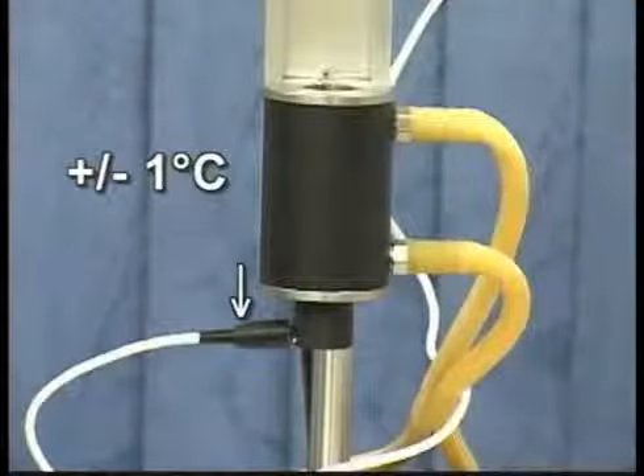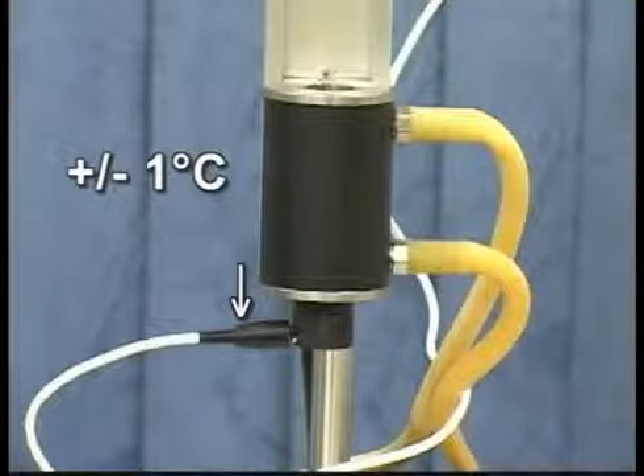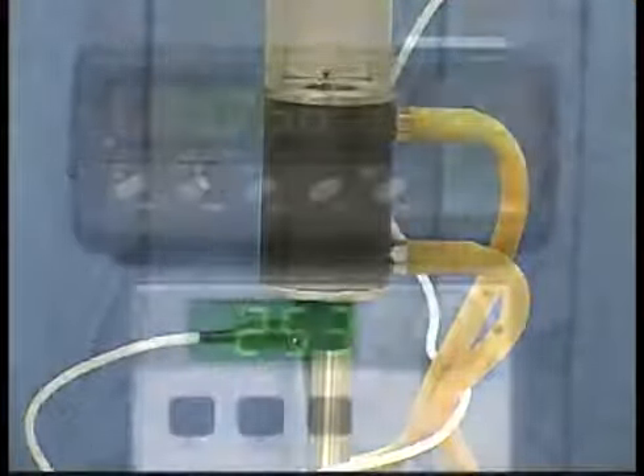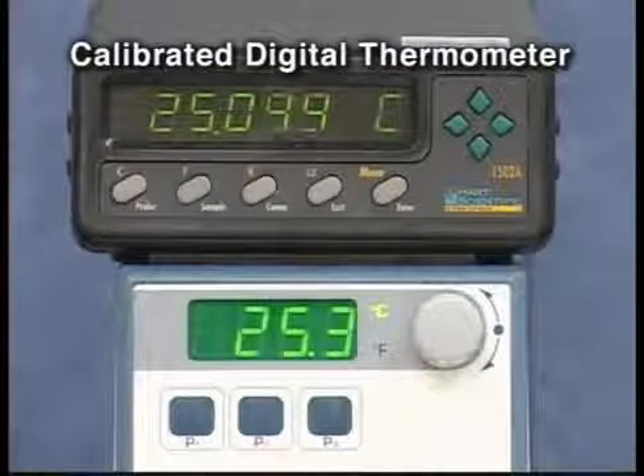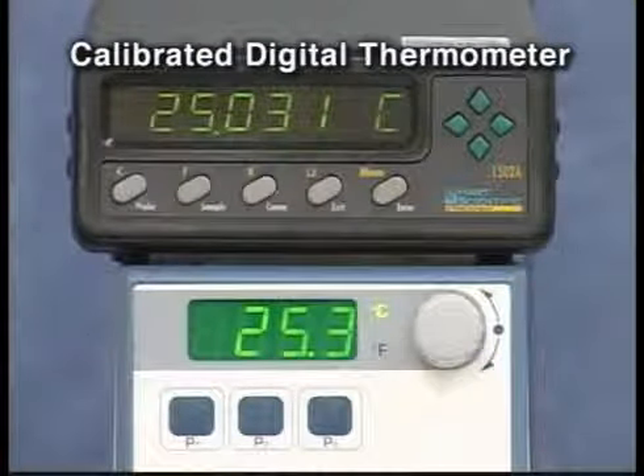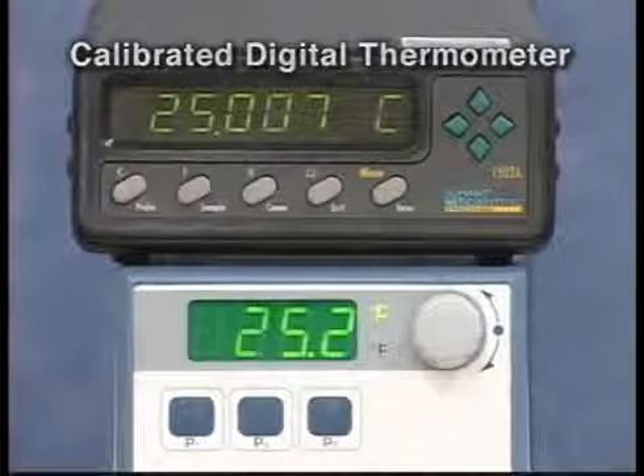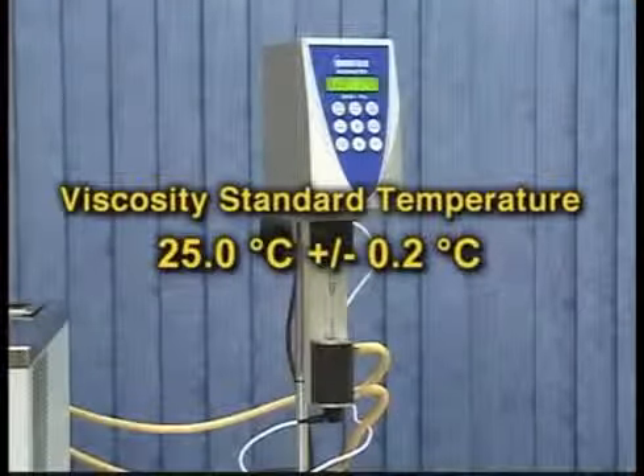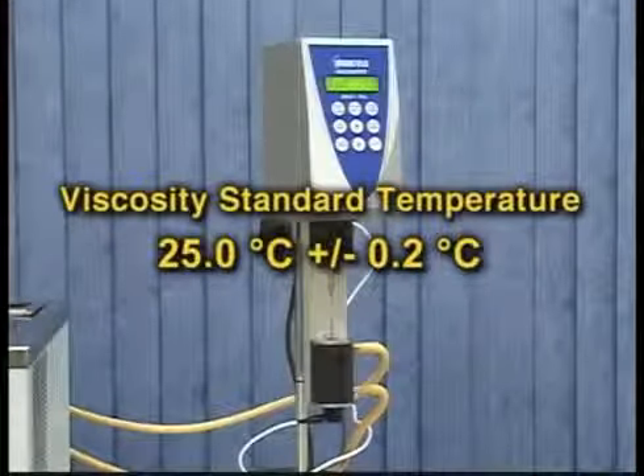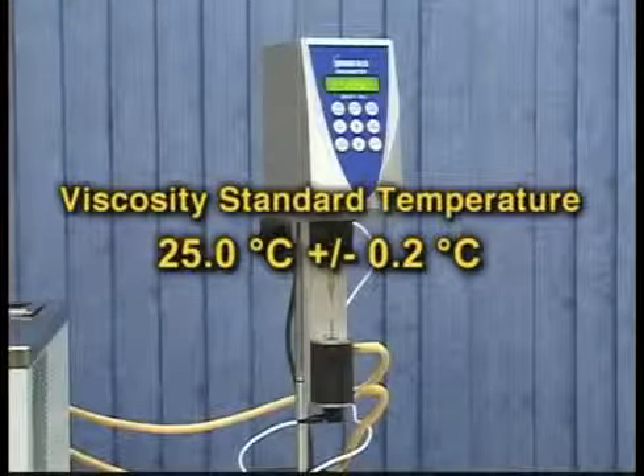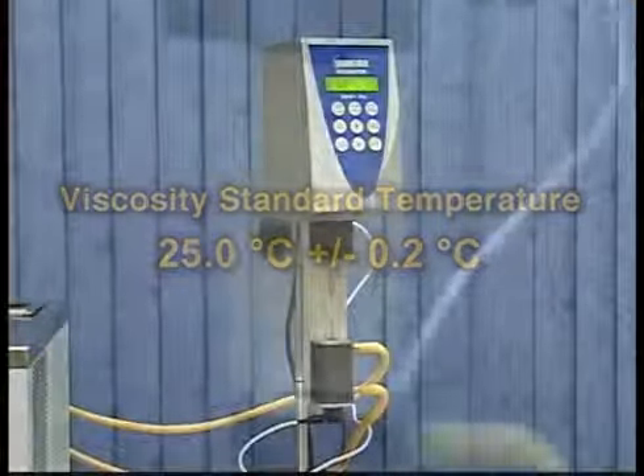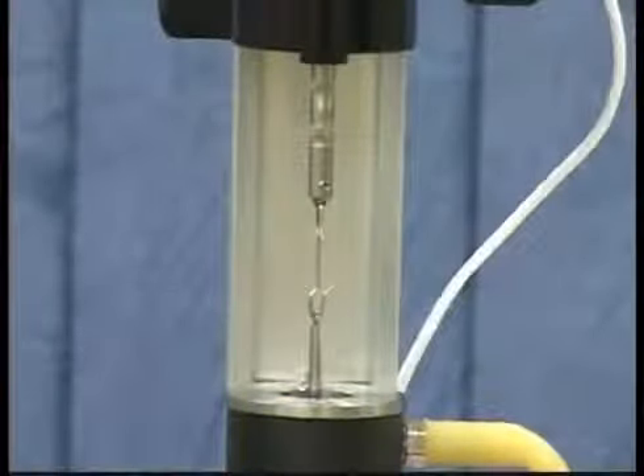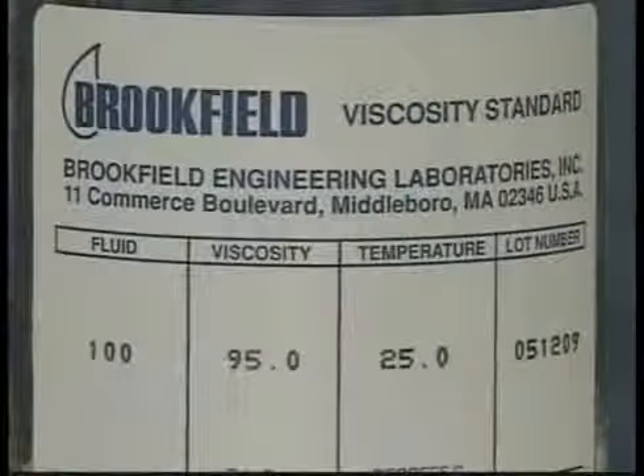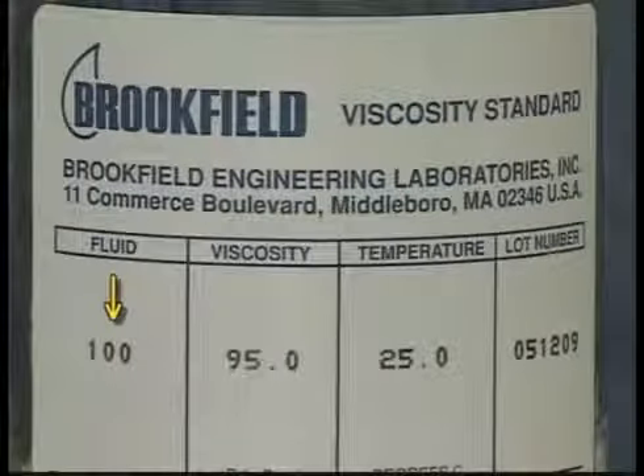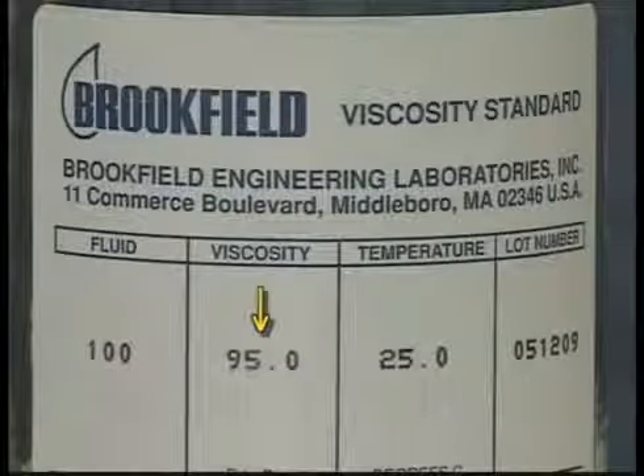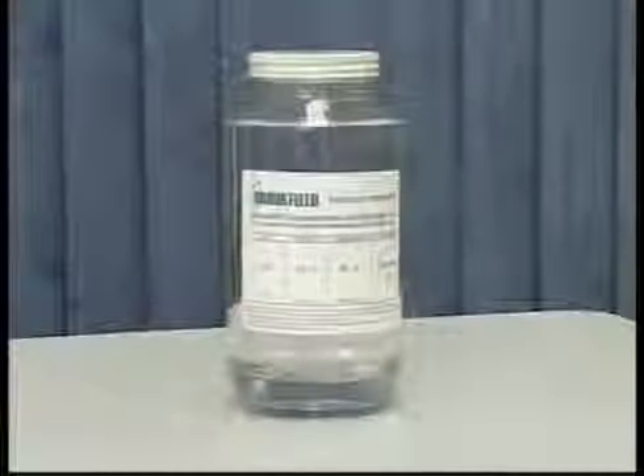The temperature probe on the Brookfield viscometer is accurate to plus or minus 1 degree centigrade. To ensure proper temperature equilibration and accuracy for the viscosity standard, use a calibrated thermometer with higher accuracy. The temperature of the viscosity standard should be controlled at 25.0 degrees centigrade, plus or minus 0.2 degrees centigrade. The thicker the fluid, the longer it will take to equilibrate. For this calibration, we will use a 100 centipoise fluid with an actual value of 95 centipoise. This should take 15 minutes.